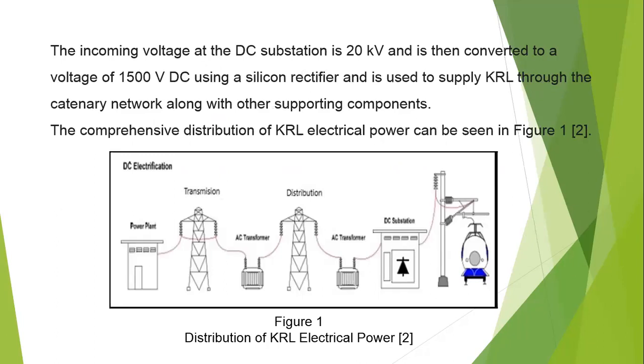As can be seen in figure 1, the incoming voltage at the DC substation is 20 kilovolt and is then converted to a voltage of 1500 VDC using a silicon rectifier and is used to supply KRL through the catenary network along with other supporting components.